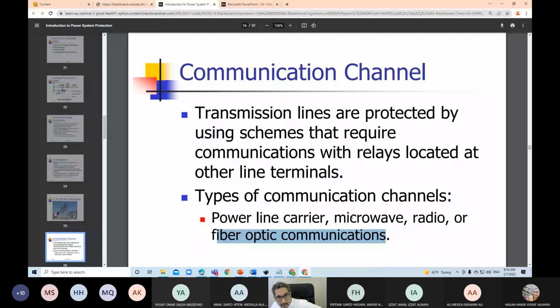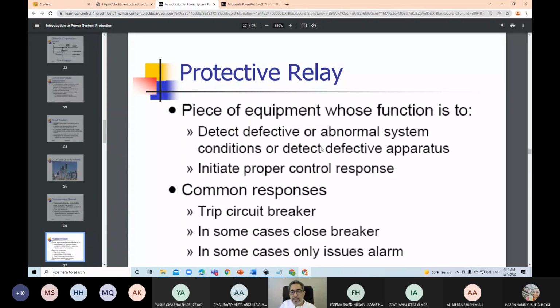So a protective relay is a piece of equipment whose purpose is to detect defective or abnormal system conditions. Its response is that it trips a circuit breaker to clear the fault. In some abnormal situations we close a breaker, if it is not a protective relay but a regulating relay. In some cases it issues alarms, as I mentioned before: we don't trip a breaker, but we issue an alarm. So generally, this equipment is a reactionary device. It does not predict that there will be a fault, and we take actions.